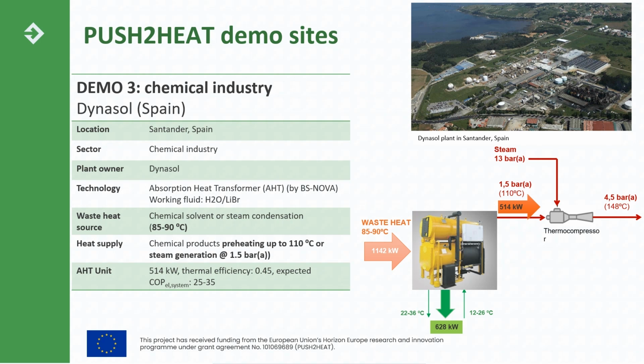So taking this heat, this will be around 1 megawatt of waste heat at around 89 degrees centigrade. This will be used to activate the absorption heat transformer, and we will get as an output around 500 kilowatts of heat. Depending on where it is decided to implement this heat pump, the delivered heat will be used to preheat the chemical product up to 110 degrees centigrade.